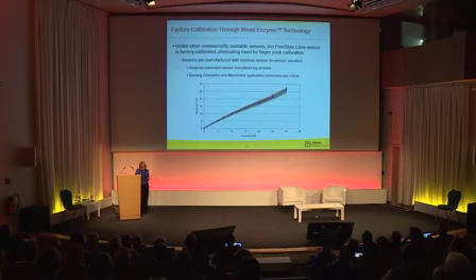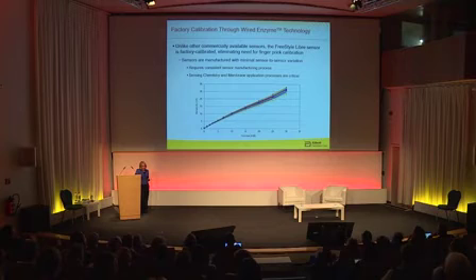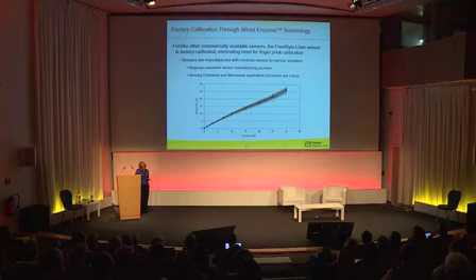Unlike other commercially available sensors, the FreeStyle Libre sensor is factory calibrated, eliminating the need for finger prick calibration. The sensors are manufactured with minimal sensor-to-sensor variation, and this requires a consistent manufacturing process. The sensing chemistry and membrane application processes are critical to this.